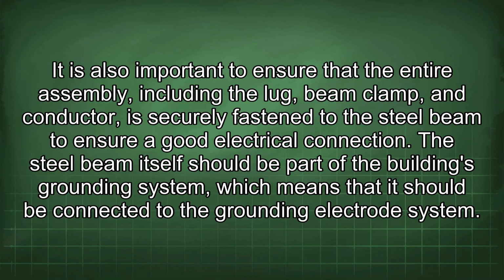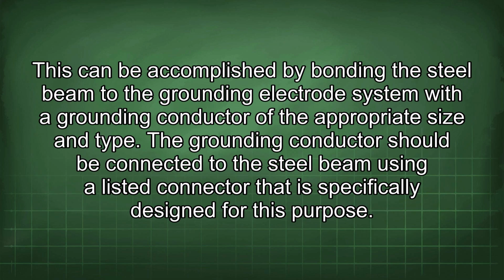The steel beam itself should be part of the building's grounding system, which means that it should be connected to the grounding electrode system. This can be accomplished by bonding the steel beam to the grounding electrode system with the grounding conductor of the appropriate size and type. The grounding conductor should be connected to the steel beam using a listed connector that is specifically designed for this purpose.